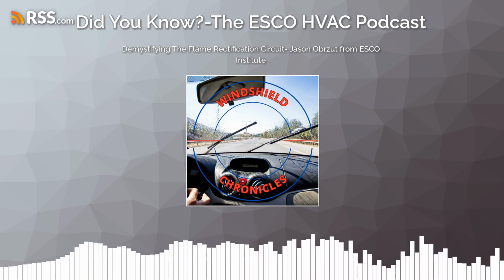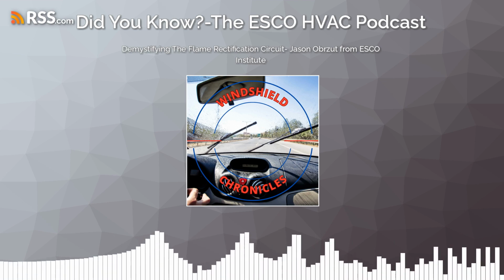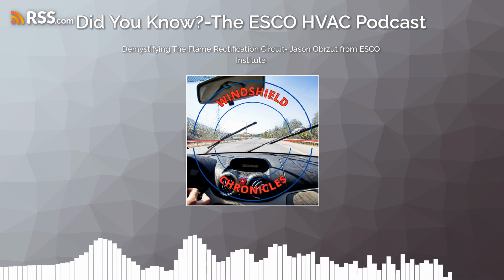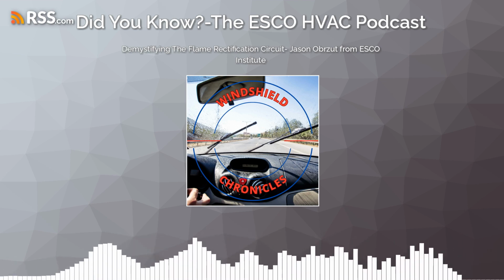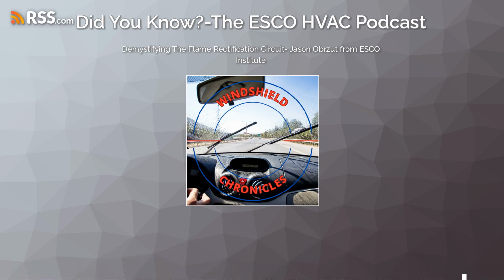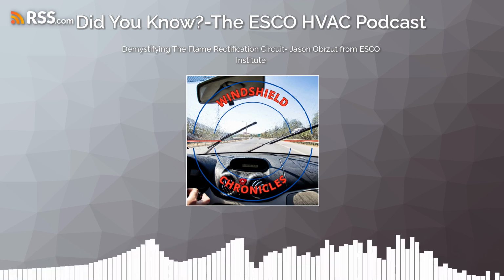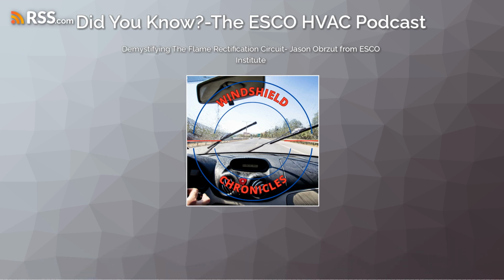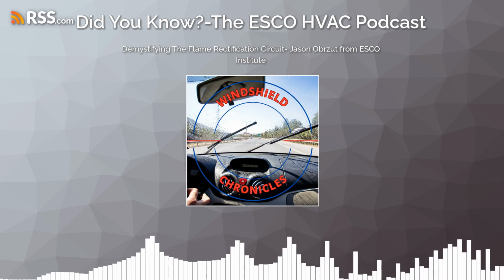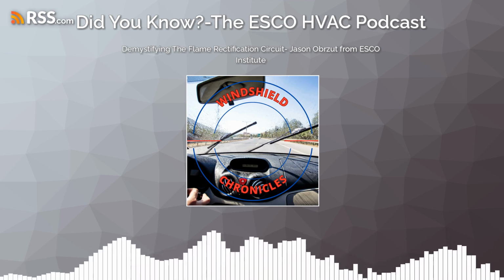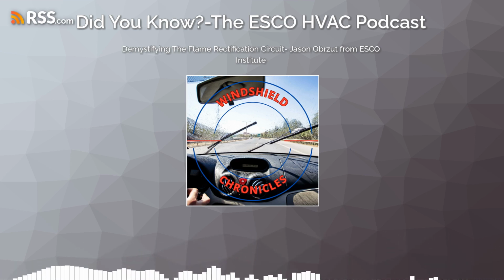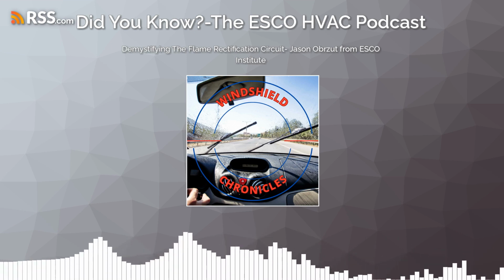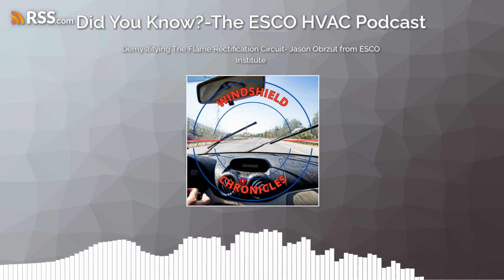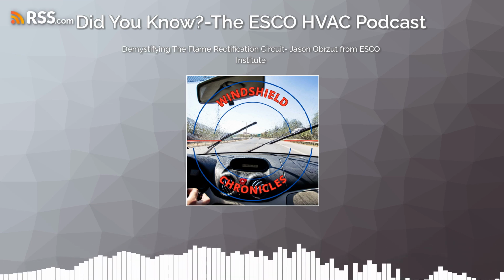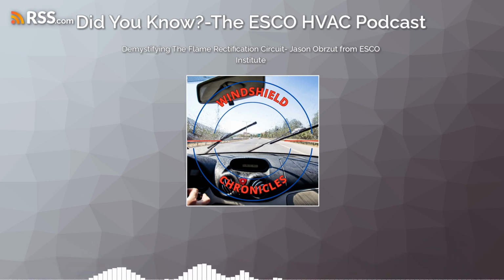If we look at this wiring diagram, my flame sensor, the manufacturer is actually calling it a flame sensor. I'm going to call it a rod because it's not sensing anything. It's just a rod made of Kanthal. But if you look, it is on the high side of our transformer. It is on the same side of our transformer as our hot surface igniter, our induced draft blower, and our circulating blower. The only difference is our voltage has been reduced to typically a lower, safer voltage rating for handling. But it's actually AC voltage.